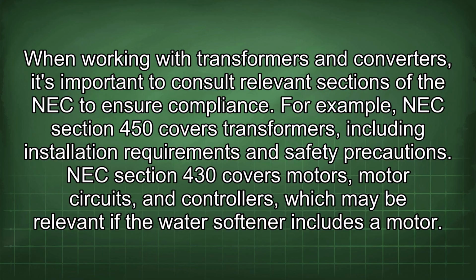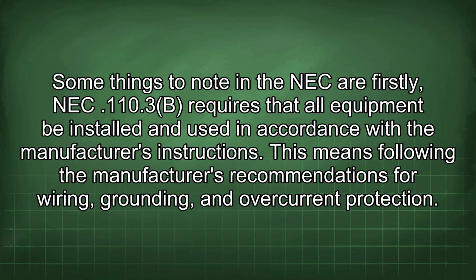For example, NEC Section 450 covers transformers, including installation requirements and safety precautions. NEC Section 430 covers motors, motor circuits, and controllers, which may be relevant if the water softener includes a motor. Some things to note in the NEC are firstly, NEC 110.3(B) requires that all equipment be installed and used in accordance with the manufacturer's instructions. This means following the manufacturer's recommendations for wiring, grounding, and overcurrent protection.